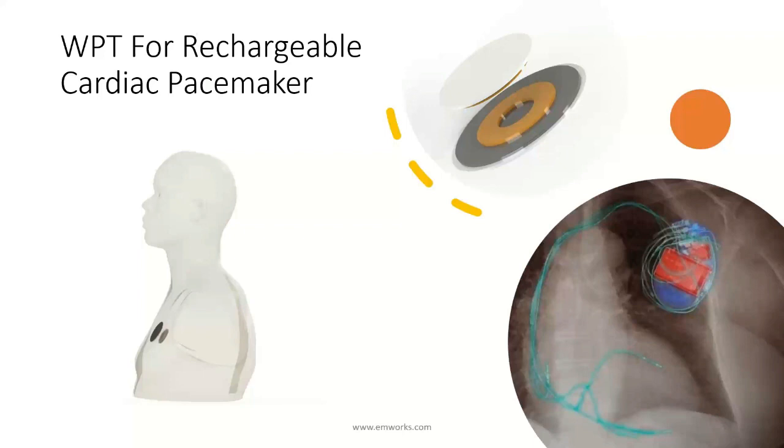However, while this rechargeable pacemaker offers quite interesting advantages, its wireless charger can present some weaknesses like low efficiency and high power loss. They may also cause high electromagnetic radiation, and this can lead to electromagnetic interference issues, whether with the human body or electronic devices.